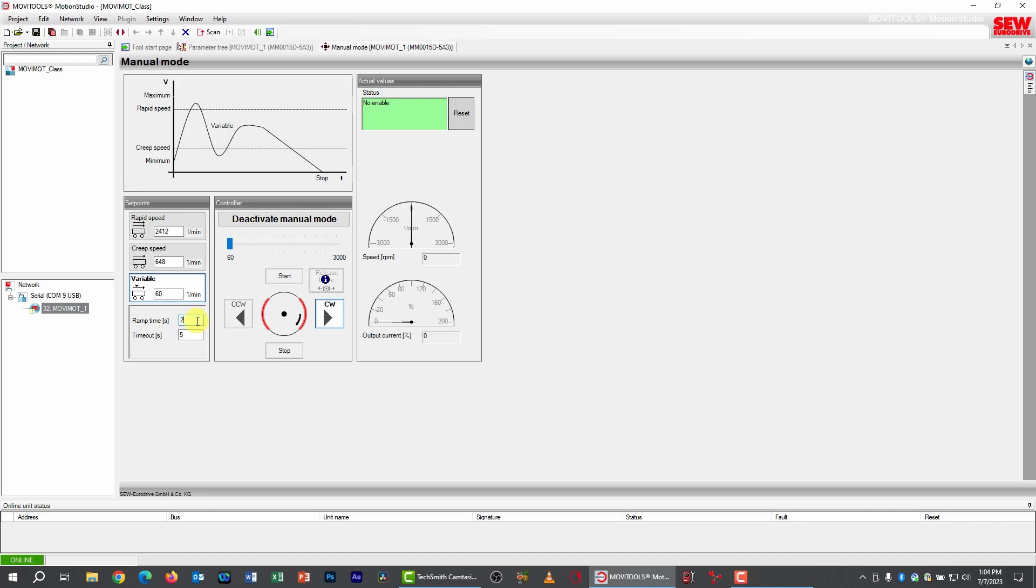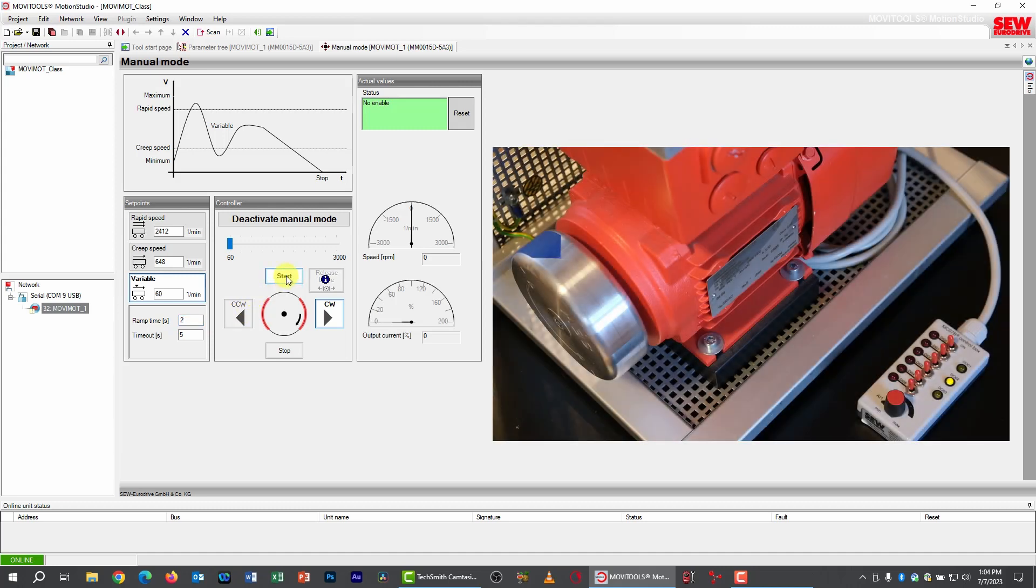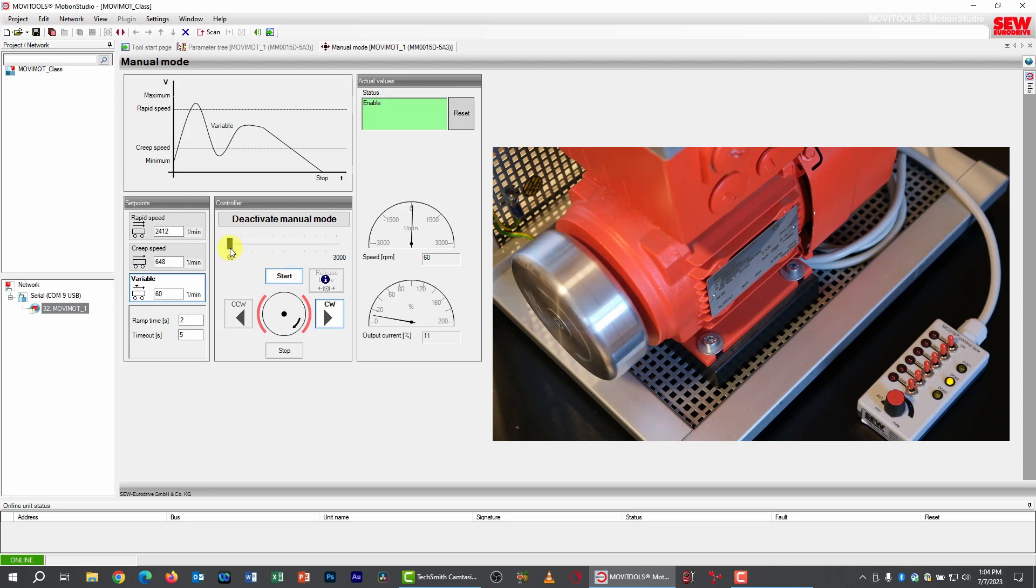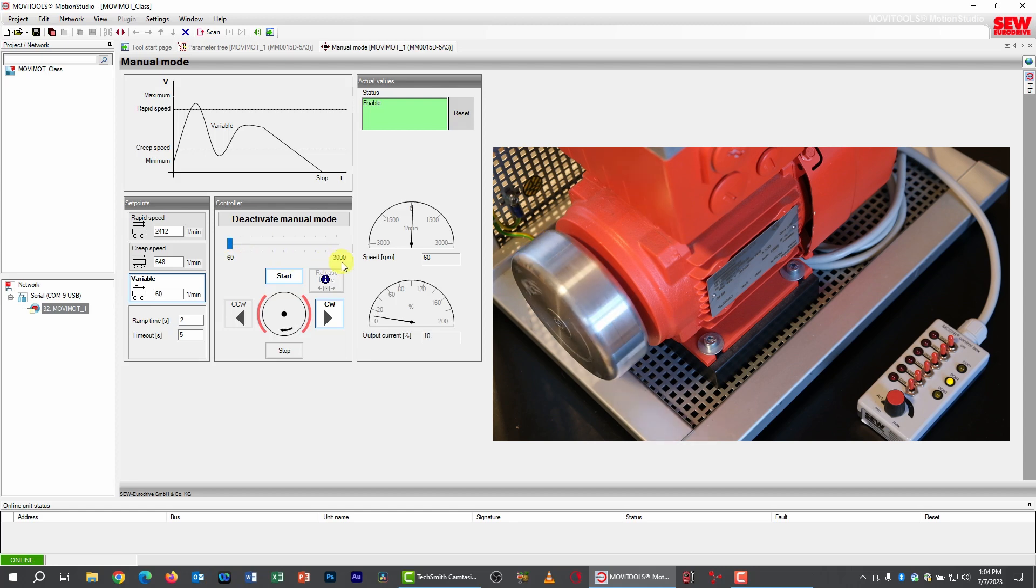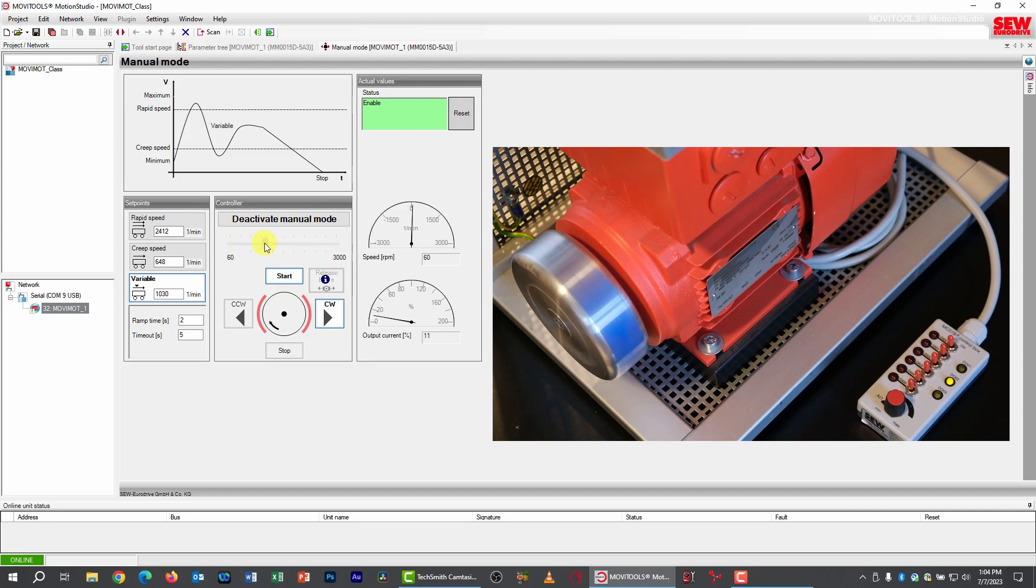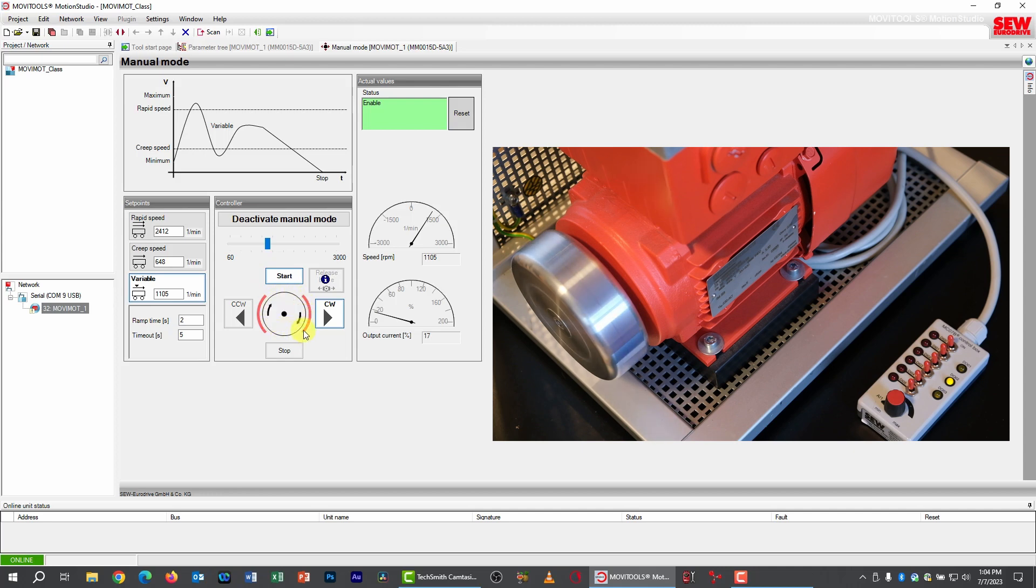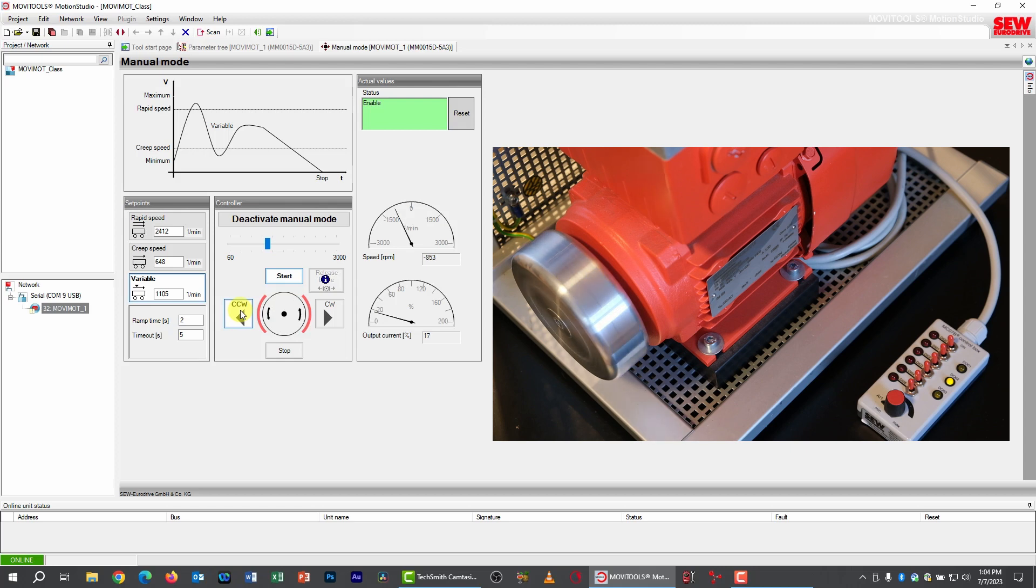Let's go ahead and start our drive up and run it and see it in operation. So I'll click Start. And you can see that's enabled our drive and it started turning at 60 RPM, which is the minimum speed. You may wonder where does 60 and 3000 come from? Well I'll show you that in a few minutes. I'm going to speed the motor up a little bit, so we'll just move the slider and you can see the motor speeds up. Notice that the motor diagram is now rotating and the two brake symbols show that the brake is released. I'll reverse direction here by clicking counterclockwise and we'll go the other way.